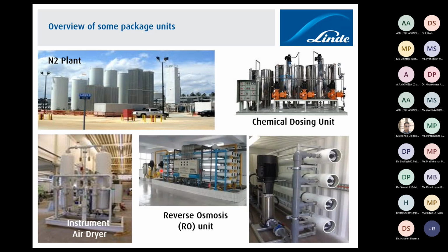Chemical dosing unit, you have already seen this image. Reverse osmosis unit. Another way of doing demineralization nowadays is reverse osmosis. Reverse osmosis widely caters to a range of total dissolved solids, from 10,000 and even more than 10,000 in seawater application, in brackish water application, and in a typical industrial waste where you have some 1,000 or 1,500 TDS, or usually river water ranging from 500 to 1,200 TDS. So for all kinds of application you can produce DM water straight away by putting a number of stages on a product staging or a reject staging. We can achieve this via a reverse osmosis plant.